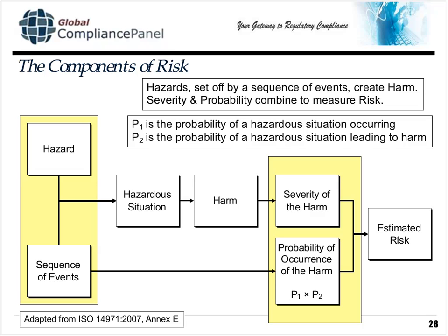And we're going to look at severity, and we talked about burns already. So burns have a nice severity classification, first, second, and third degree. Burns have various levels of severity, and so if we're interested in a first-degree burn, then we might talk about the probability that a first-degree burn is the harm. We might talk about a second-degree burn, and it's going to have a different probability because a second-degree burn is less likely, we would like to think in most instances, to happen. So first-degree burns might be more common, second-degree burns less common, third-degree burns extremely rare, we would like to think. So the severity and the probability are going to go together. We're going to combine them in our method to estimate risk.